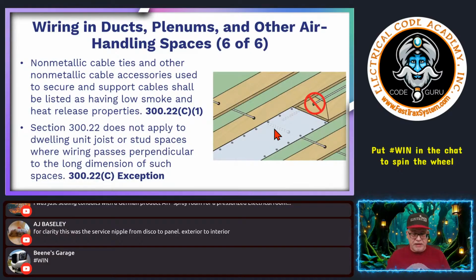In residential applications, a lot of times they'll use a joist bay as a return, for example, and they'll use it to pull air back because it's basically like a duct. You've got sheetrock on either side and this cavity, and they just cut it right into the sheetrock and put the grill on there. You can have non-metallic sheathed cable run perpendicular, but it cannot use that cavity. So if you have any NM cable running up the side of these joists or up the side of framing studs, it cannot be in that space. Now, can it run across perpendicular? Absolutely. It just cannot run in the space.